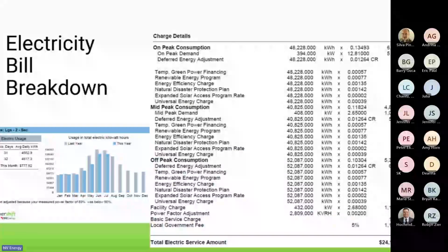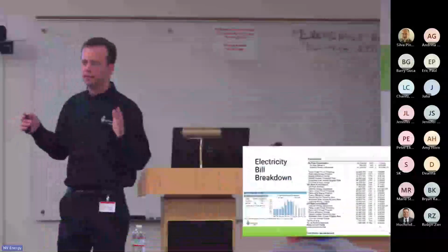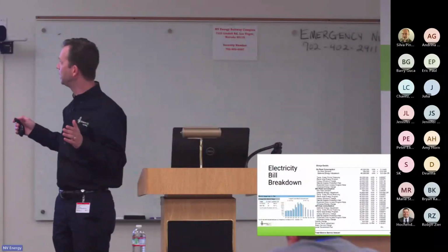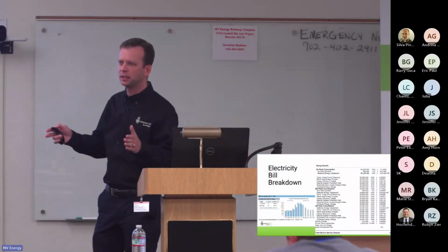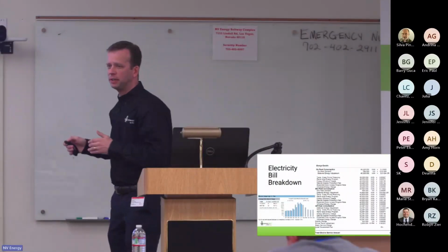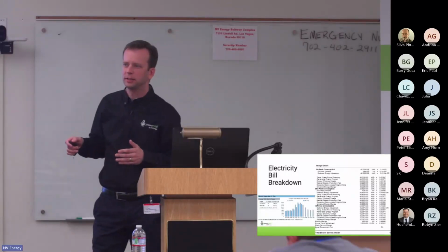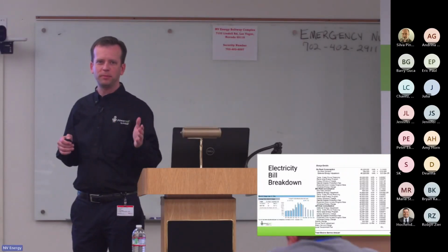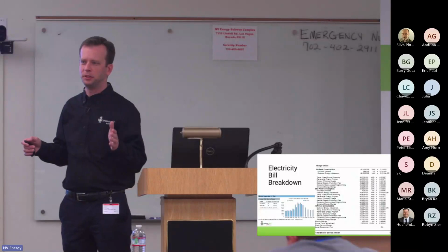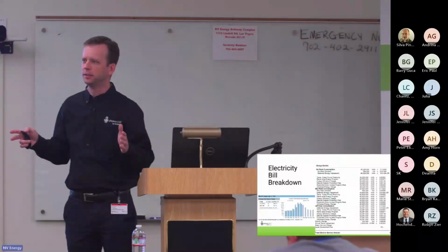Particularly, what I'd highlight is on the top row, your on-peak consumption, $6,000 here. Your on-peak demand—again that's a 15-minute window—so in 15 minutes they averaged 394 kW. Because of that, they paid $5,000 that month. On-peak is 1 p.m. to 7 p.m. between June 1 and September 30.